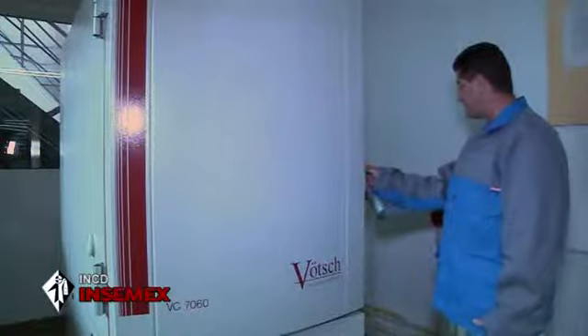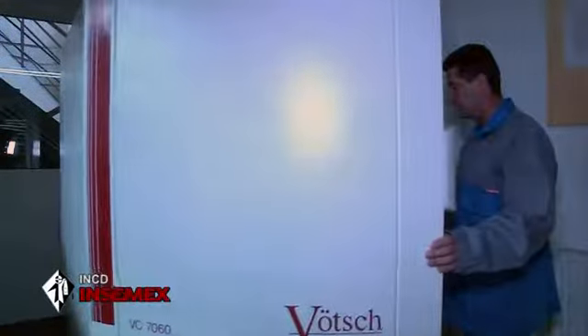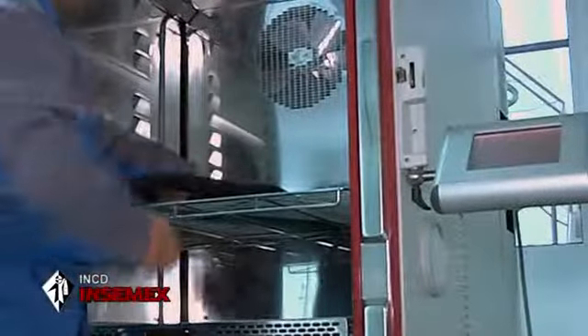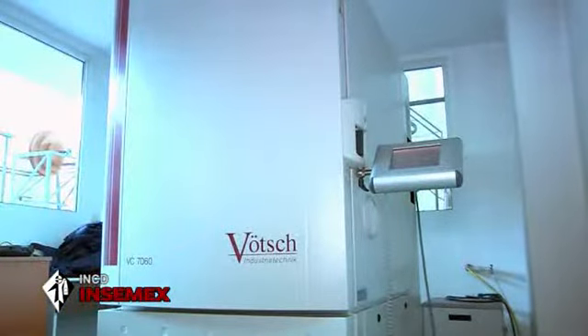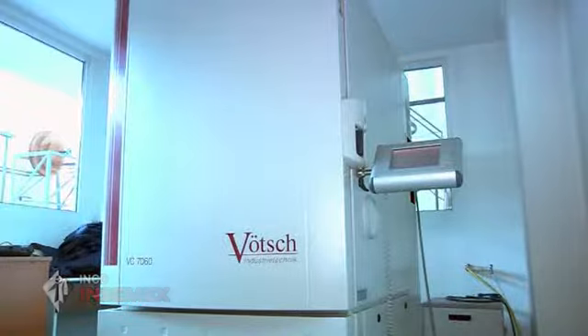The climatic test chamber type Vötsch VC 7060 is able to perform temperature conditioning ranging between -70 degrees Celsius and +180 degrees Celsius, and humidity conditioning ranging between 0 and 99%. The space used for conditioning is 600 cubic decimeters. There is also a possibility for conditioning certain equipment during their operation, for example lamps or LED projectors.